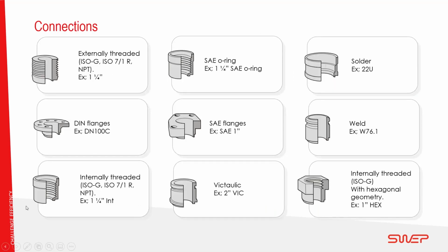In terms of connections, we have pretty much connections to suit most applications. In HVAC, the most common would be an externally threaded or a DIN flange. But then for other circumstances, we've got internal threads, SAE flanges for automotive applications and also for the rail industry. Victaulic, I'm not seeing it used so much in the UK, but it's very common in Europe. We also use that to join heat exchangers together if we're putting more than one in series. And then, of course, we have solder weld for the refrigeration industry.